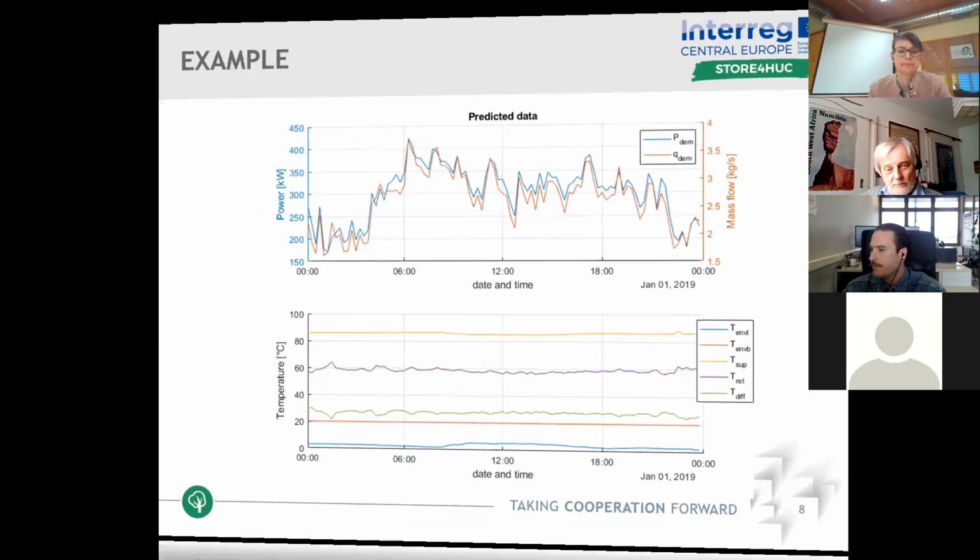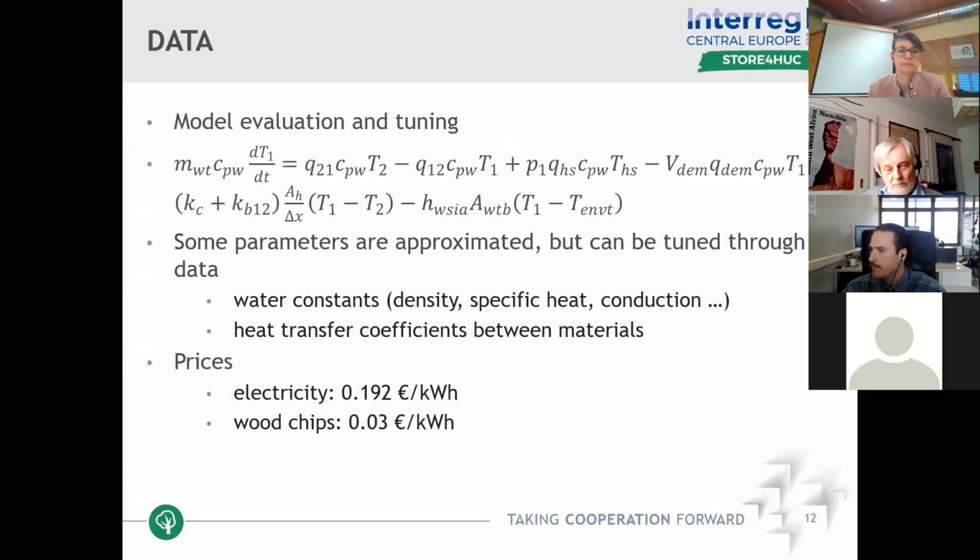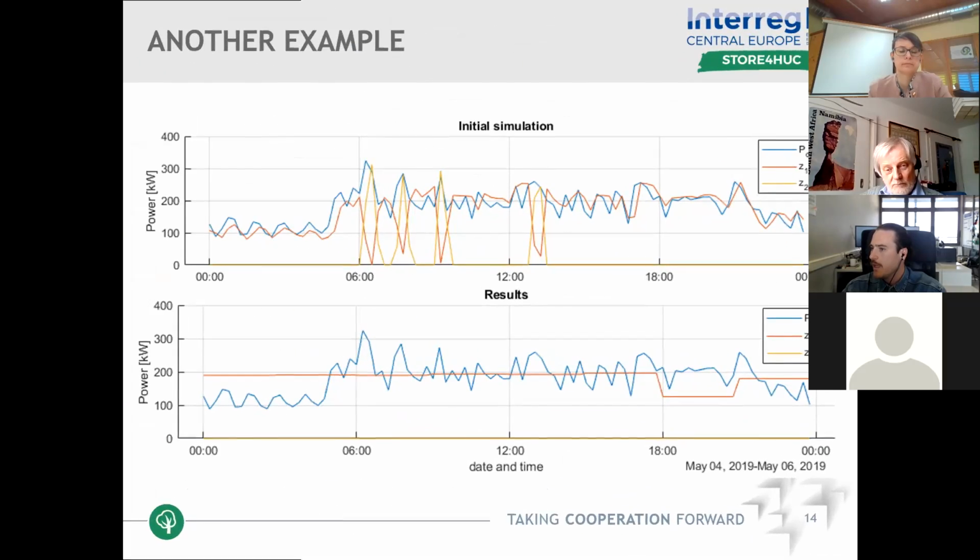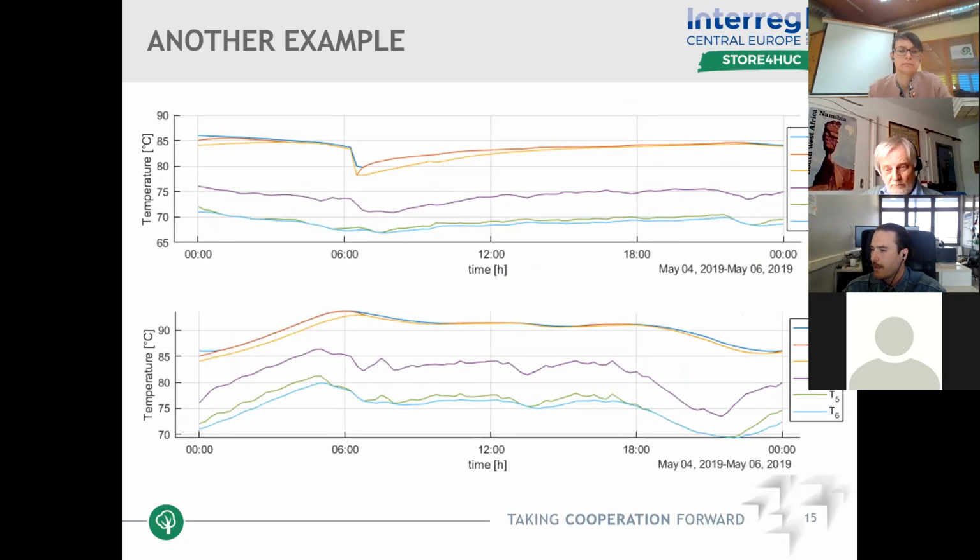So I think it should not make up too much, but if you have the whole year, it probably has some influence. Yes, as from the simulated part, the outside air doesn't have much influence on these temperatures, but it still should be modeled. This heat transfer coefficient that we use might not be accurate. I see that there's a vast range of values that can be used. So if you have measurements, we can adjust it accordingly. But yes, it is modeled in here. Okay, thank you.